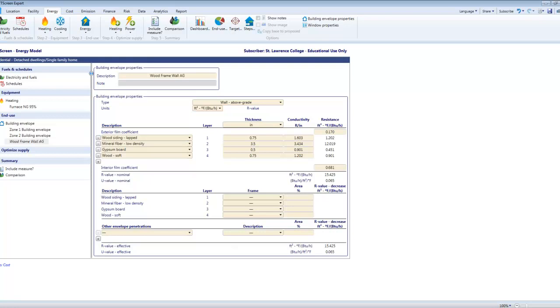Now, if you're thinking about the structure of this wall, you'll realize that we have not modeled the studs that are in the wall. The studs are not a continuous layer, and in fact, the studs are a thermal bridge. And we model those down here. So whatever we model down here is going to be an R value decrease. And that's where the studs are going to appear. We get to choose now, of the existing layers that we've created, which layer is your thermal bridge in? Well, the studs are bridging through this mineral fiber layer here. They're effectively reducing the R value of that mineral fiber layer. If we didn't have any studs, we'd have a continuous layer of fiberglass insulation. Our studs interrupt that, and the studs have a worse R value than the insulation, and so they're going to create a thermal bridge.